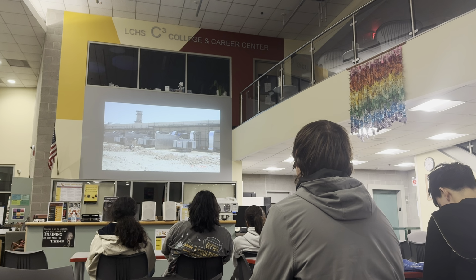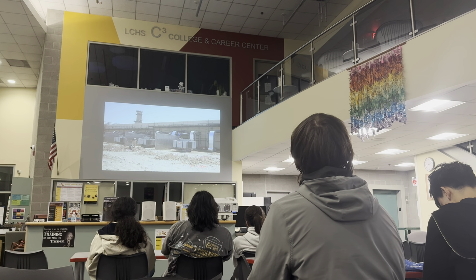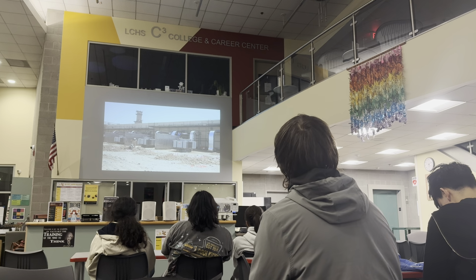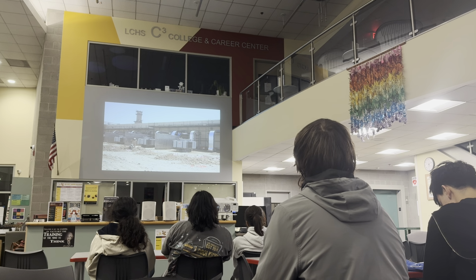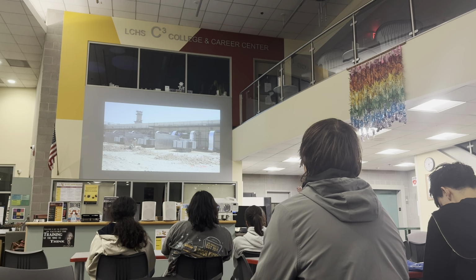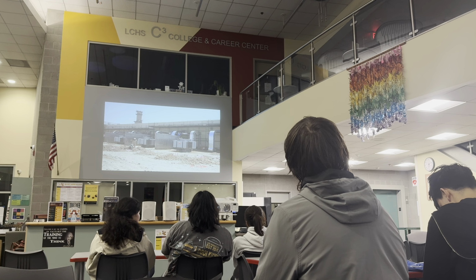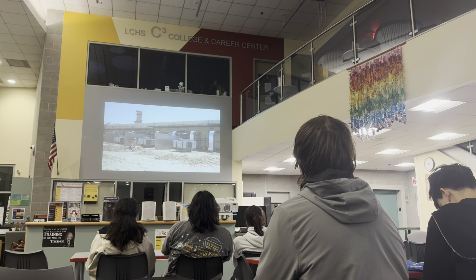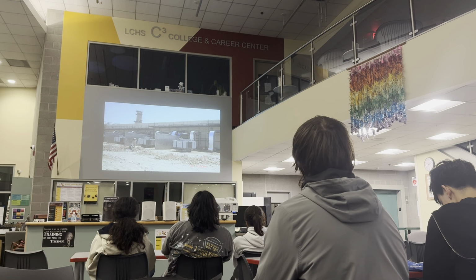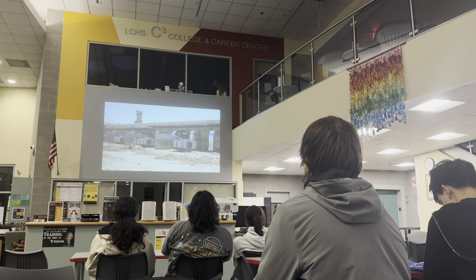Usually 115 kV power comes in, goes into the transformer, and goes down to 13.8 kV. Usually these facilities work with 13.8 kV and below. But what comes in from the utility is higher than 13, so you have to bring it down. So it's a transformer. Now, everybody knows why we have walls between transformers? These transformers usually explode. If there is a malfunction or something, it catches fire or explodes. So they put the walls so it doesn't damage the next transformer. So it's a standard. You have to put this wall between power transformers.